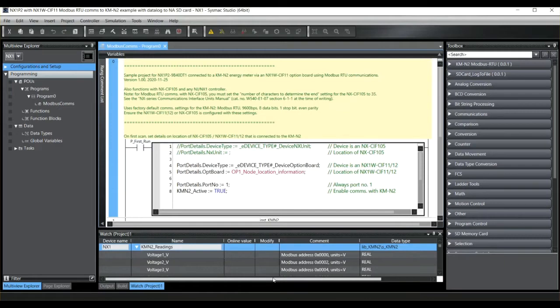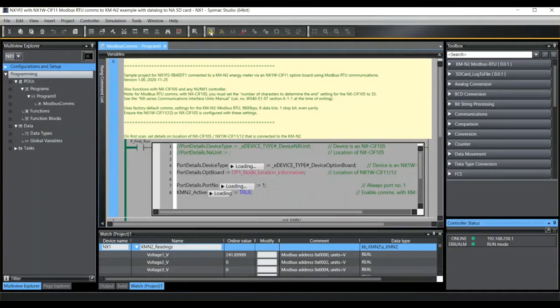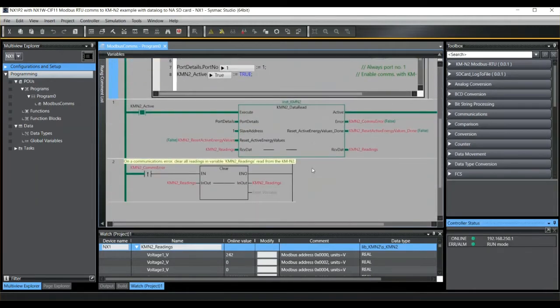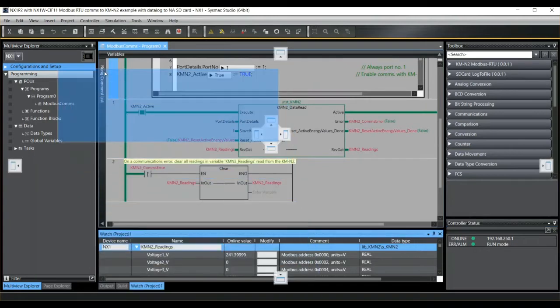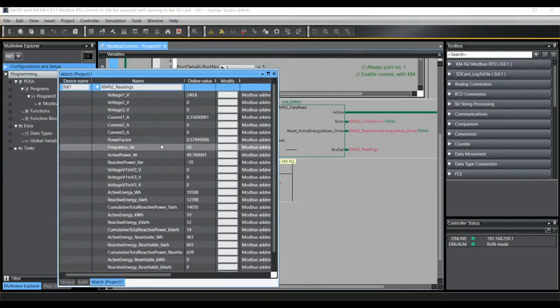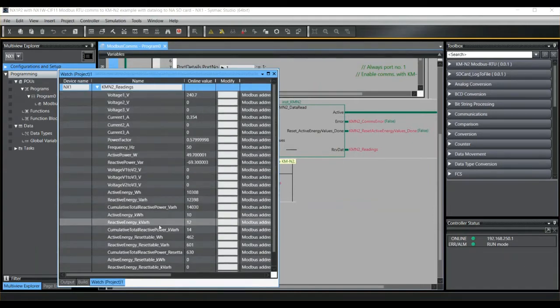In the previous video we showed how to set up and achieve communications from an NJ or NX machine controller to a KM-N2 power monitor to access power consumption readings. If I go online with my NX1P2, we have this function block here that's reading KMN2 values into this variable called KMN2 readings. We can see these values in this watch window here: voltage, current, frequency, active power, and so on.